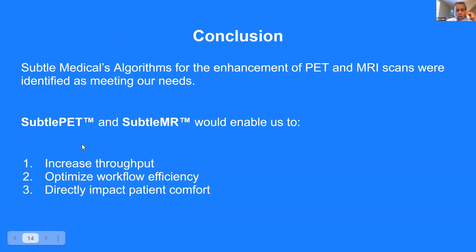Can you speak to the ACR accreditation for the products? We did work with ACR in terms of your site's equipment accreditation and the Subtle MR enhanced images. If you submit them as part of your accreditation, they will pass. We worked with both the ACR accreditation committee directly and also third-party accreditation firms like West Physics who do accreditation phantom scans. Their physicists approved the quality of the images, so it will pass ACR accreditation.